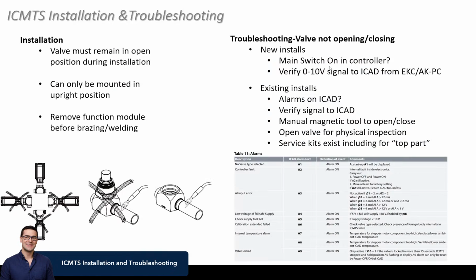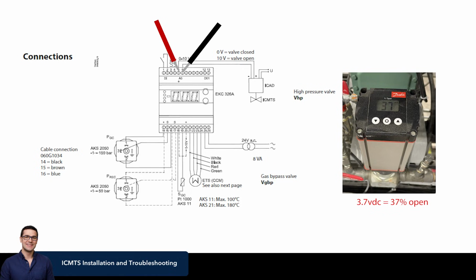Yep. For troubleshooting it, like we've been talking about these last few slides, the main switch is again something that we start with. It's an easy check. It's something that we can look at right away on a new install. Sometimes guys just aren't familiar with the fact that they need to do that. And then from there, we'd move to that 0 to 10 volt signal coming out of whichever controller we're using to go to the ICAD.